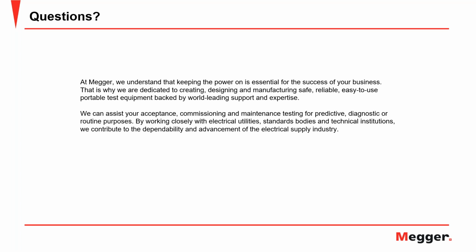I will now come back to the question on the humidity. So the question is, what is considered to be high humidity, 50% or above? Typically, it is considered that whenever you have a humidity more than 50%, you should try to avoid doing the testing. I do realize that there are parts in the world where humidity is always going to be more than 50%. In those cases, you are limited with what you have available. But as I mentioned, anytime the humidity is more than 50%, it can impact your measurement.